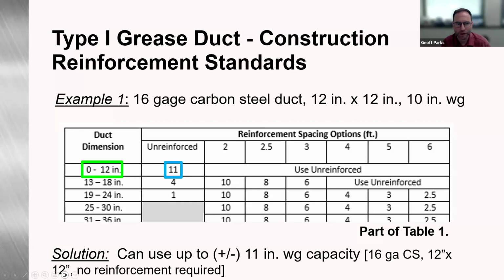So if we looked at an example here, a pretty easy one. Again, all these examples are going to be 16 gauge carbon steel. So this first one, we're saying, hey, we're going to build a 12 by 12 kitchen grease duct, 10-inch water gauge. We would come to table 1, check out our duct dimension here. And then again, our unreinforced capacity is going to be 11-inch water gauge. So our solution is we can use up to 11-inch water gauge, 16 gauge carbon steel, 12 by 12, no reinforcements required. So that's a pretty simple solution.